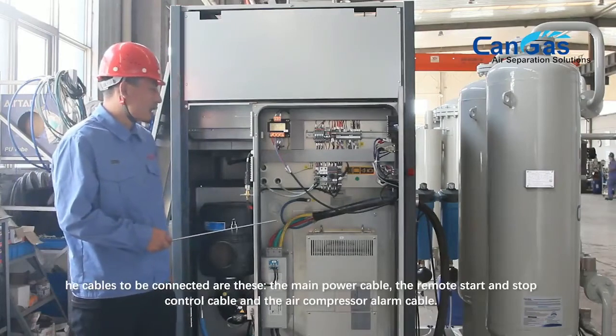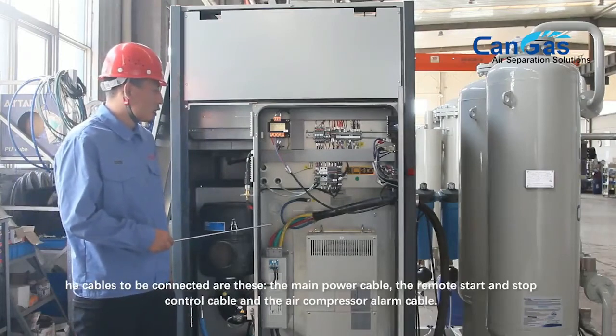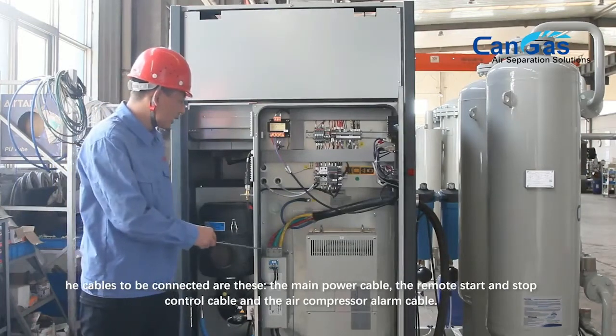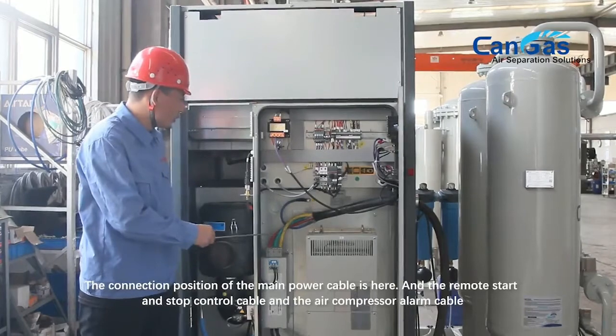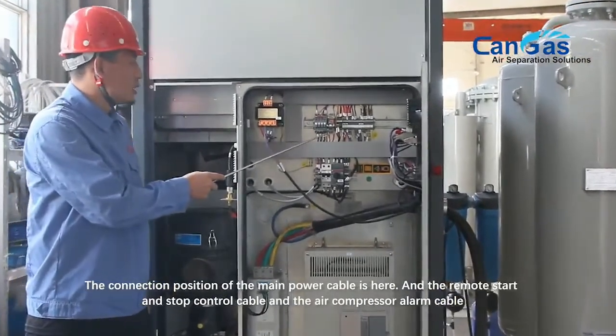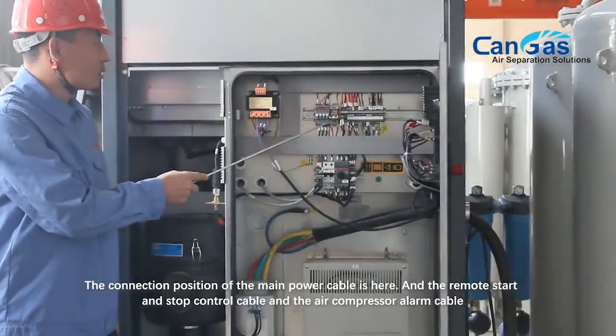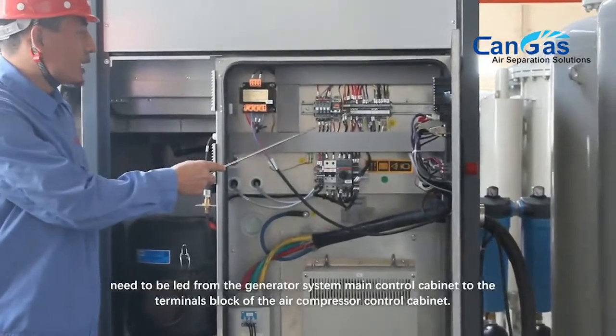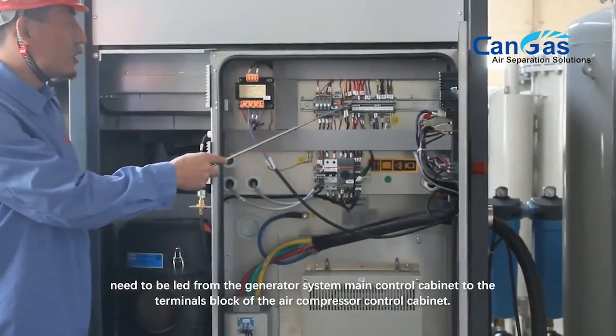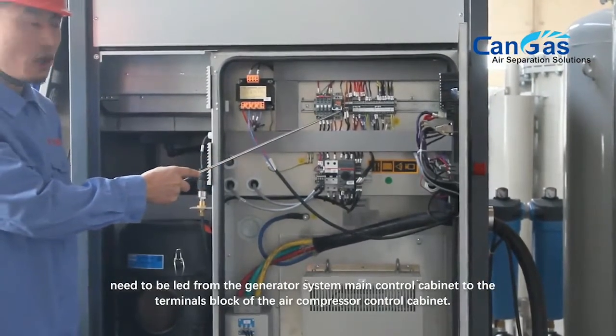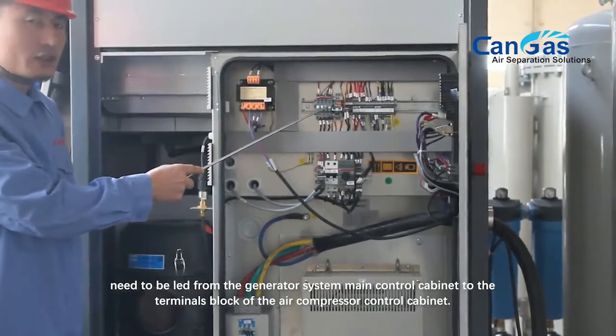The cables to be connected are these: the main power cable, the remote start and stop control cable, and the air compressor alarm cable. The connection position of the main power cable is here, and the remote start and stop control cable and the air compressor alarm cable need to be led from the generator system main control cabinet to the terminals block of the air compressor control cabinet.